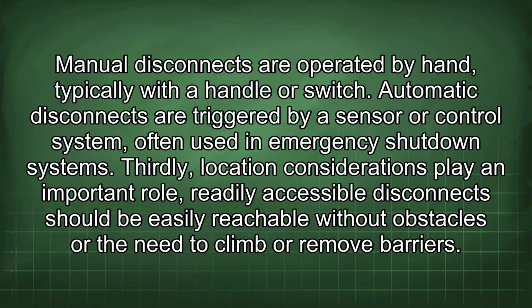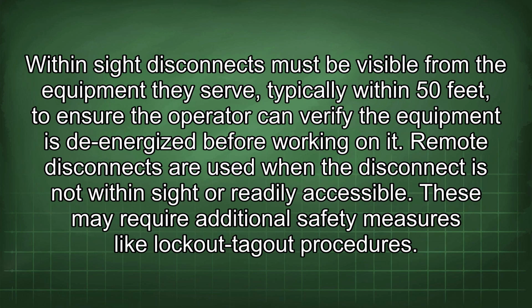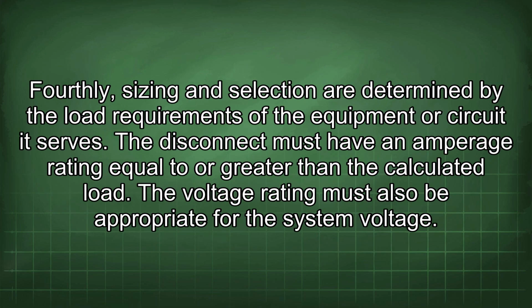Thirdly, location considerations play an important role. Readily accessible disconnects should be easily reachable without obstacles or the need to climb or remove barriers. Within-sight disconnects must be visible from the equipment they serve, typically within 50 feet, to ensure the operator can verify the equipment is de-energized before working on it. Remote disconnects are used when the disconnect is not within sight or readily accessible. These may require additional safety measures like lockout-tagout procedures. Fourthly, sizing and selection are determined by the load requirements of the equipment or circuit it serves. The disconnect must have an amperage rating equal to or greater than the calculated load. The voltage rating must also be appropriate for the system voltage.